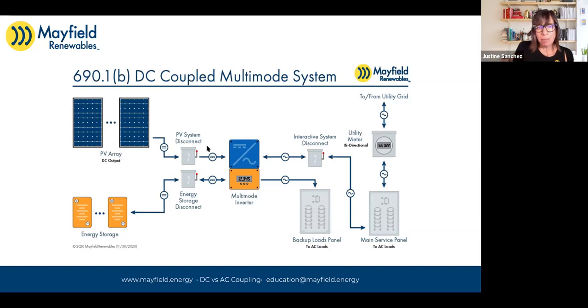Then, let's say the batteries are full and the sun is shining—now we have options with our multi-mode inverter. If we're producing more energy than we're using within our backed-up loads panel, we can send that on to the main AC panel and feed the loads in the main part of the house, or whatever we've decided to keep on the non-backed-up load scenario. And if we're using less than we're producing, that power can get sent back to the utility for a credit, just like in a normal interactive system.